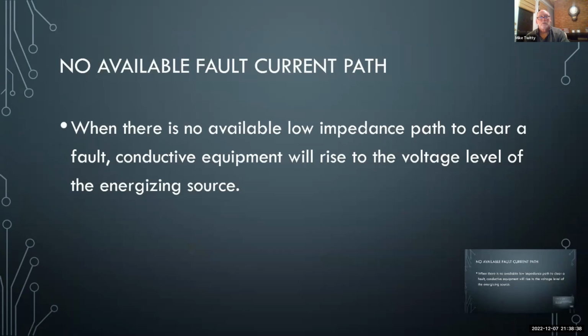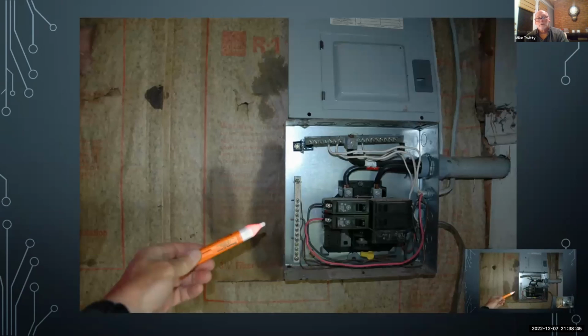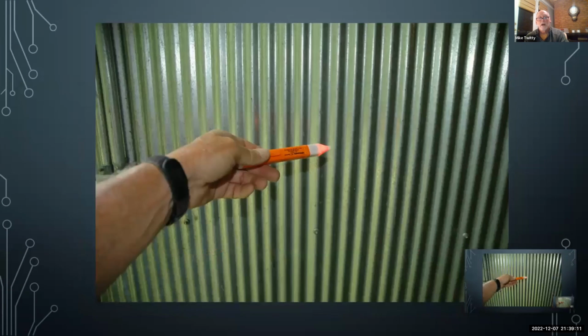Okay, when there's no path to clear the fault, the voltage will rise to the energizing level, or the energized voltage level. This is a sub panel. You can see it's a 3-wire feed. This is floating, not bonded. This was energized. A hot wire had gotten, this was all metal barn. Hot wire had gotten on a fluorescent light against the can of the light. It was all in conduit, and it energized everything in this building. I had 118 volts from this metal siding on this building to a ground rod, to the neutral. I wonder if somebody didn't get killed in there, and it didn't have any path to clear that fault.